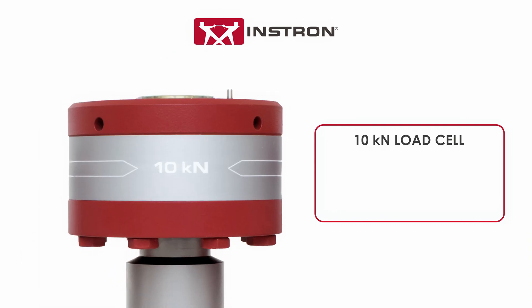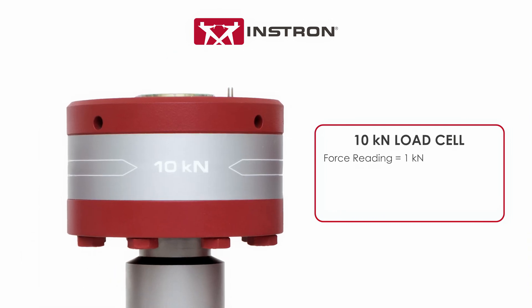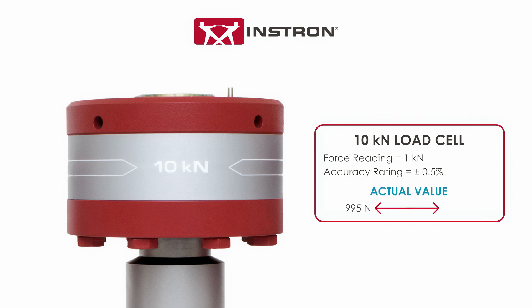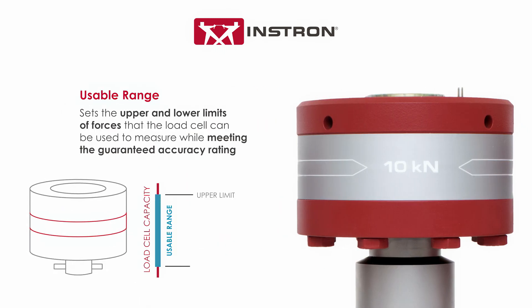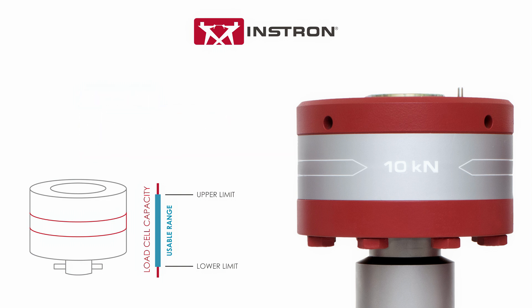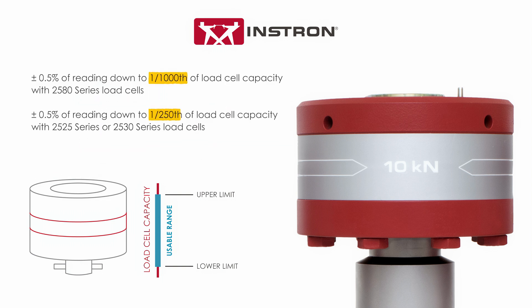In this scenario, if a 10 kilonewton load cell has a force reading of one kilonewton, an accuracy rating of plus or minus 0.5 percent would mean the actual value is guaranteed to be any value between 995 and 1005 newtons. The usable range sets the upper and lower limits of forces that the load cell can be used to measure while meeting the guaranteed accuracy rating. This is represented as a fraction of the load cell capacity in our specifications.